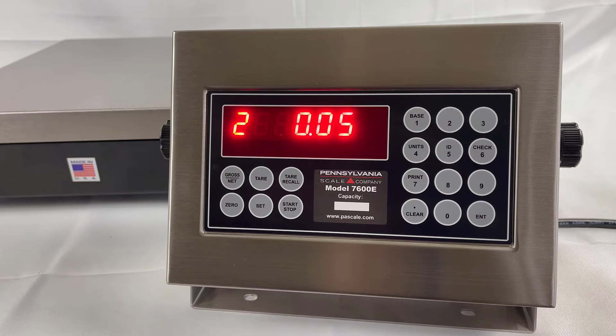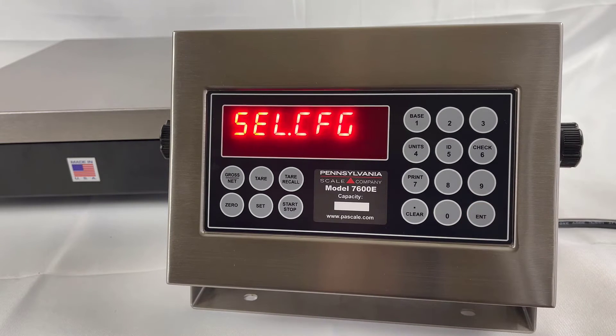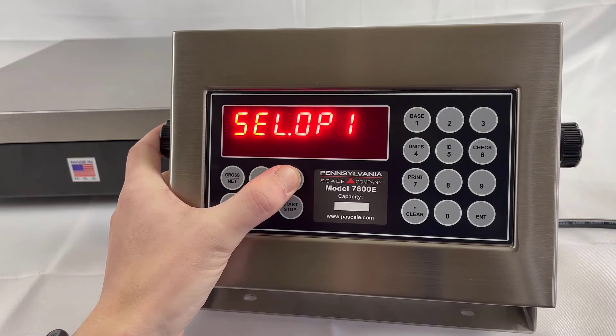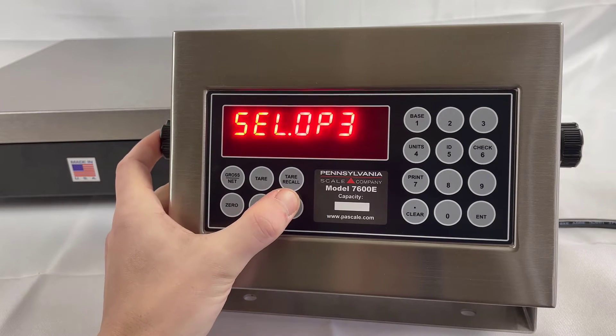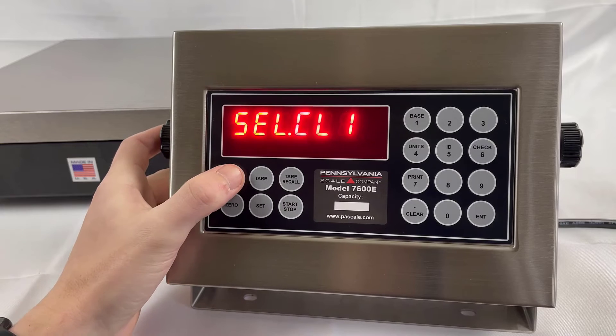You can key in a desired resolution and hit Enter, or in this case, Enter will return you to the menu. The Tare Recall key will scroll through the various menu options, and the Start and Stop key will reverse. The CL1 menu is for calibration. Gross Net will enter.